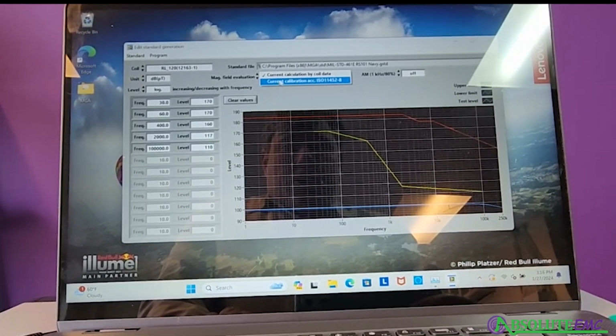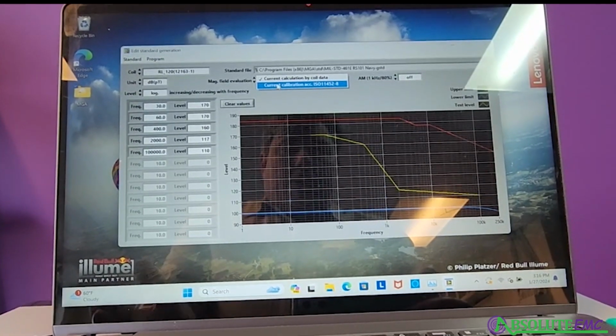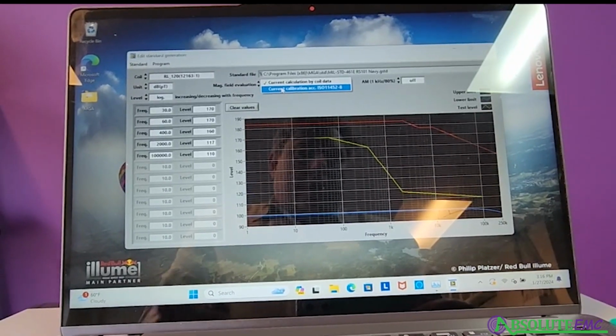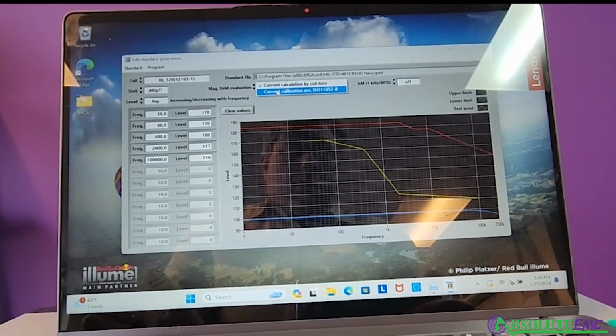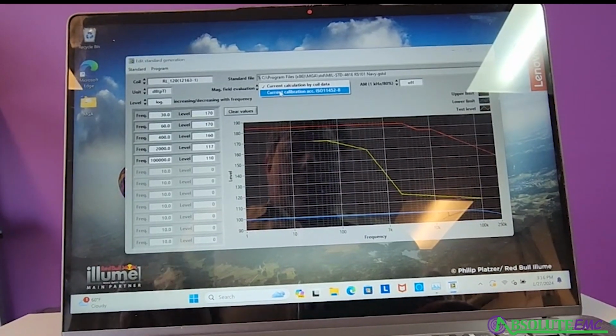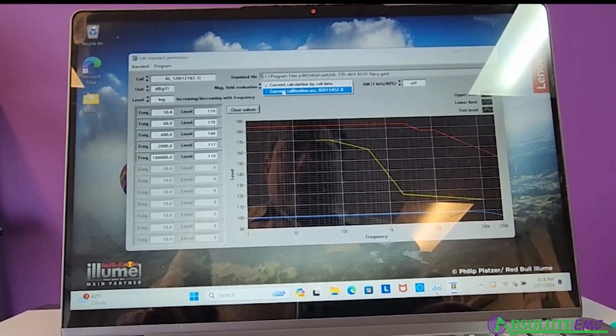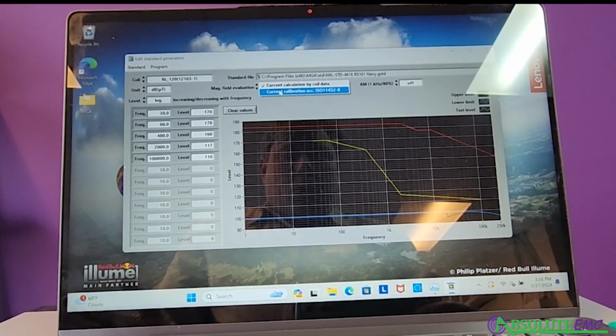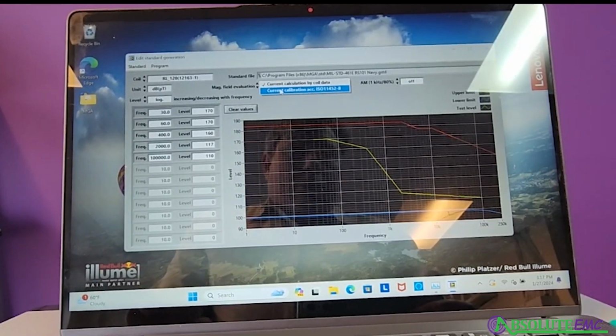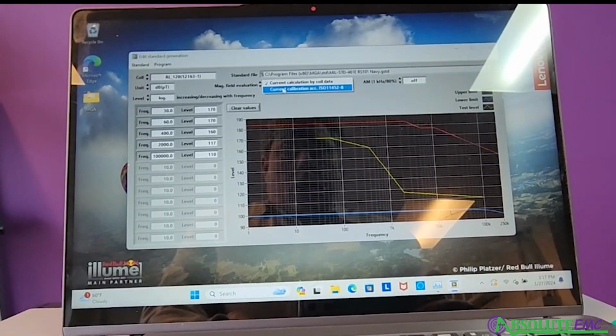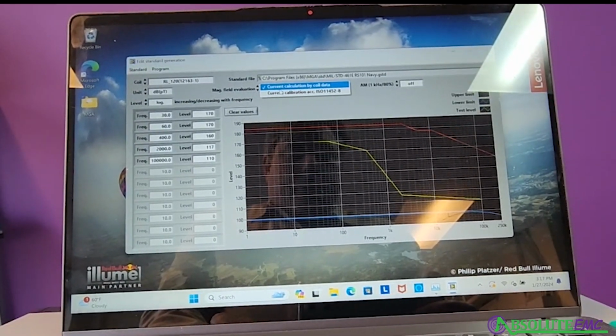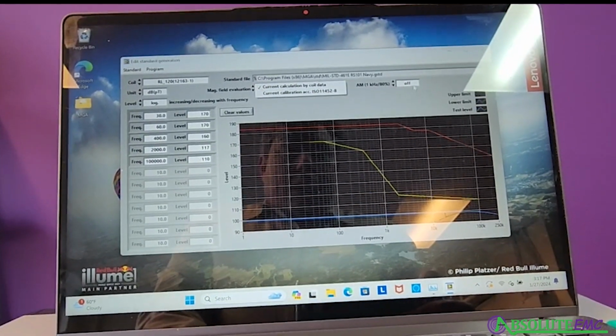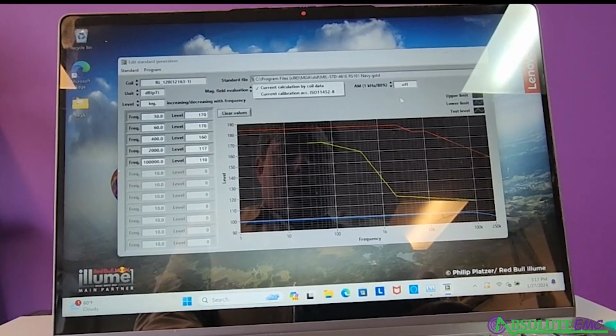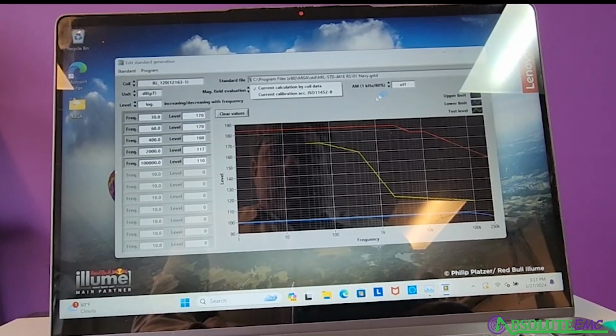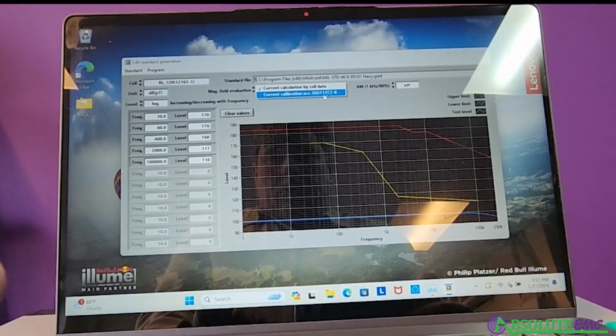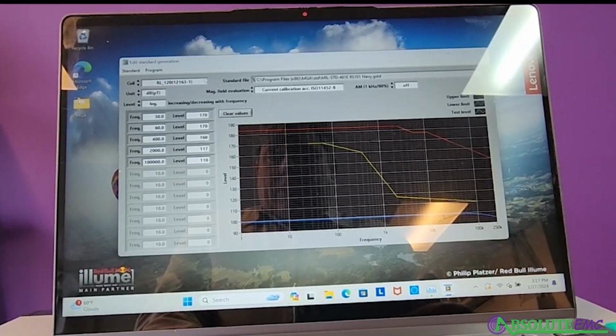So per these requirements, the coil level or the field that's generated by that coil is set directly by the current. It's pretty much straightforward: no matter what frequency or test you're at, or the level, the current is directly proportional to the field generated. Doesn't matter what frequency, but ISO 11452-8 requires a full calibration across the frequency range, which is perfectly fine. It can be done, or you can just go by the calculation of the coil, which saves a little bit of time if it's allowed. You also have the ability to do a simple modulation with AM 1 kHz 80% modulation. That's a requirement in one of the EN standards. So we're going to do the current calibration so we can see something happening here.